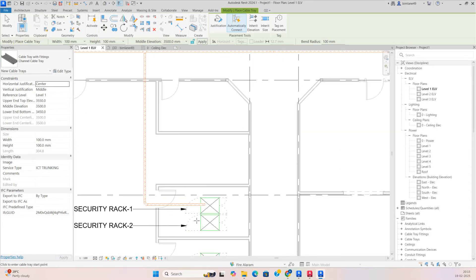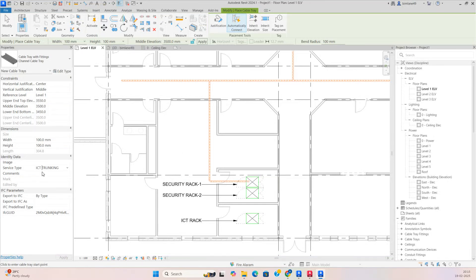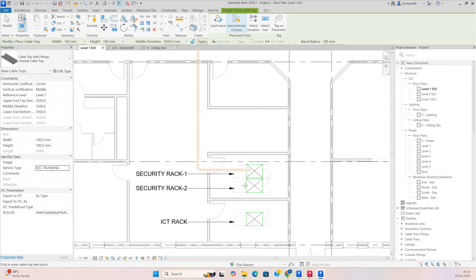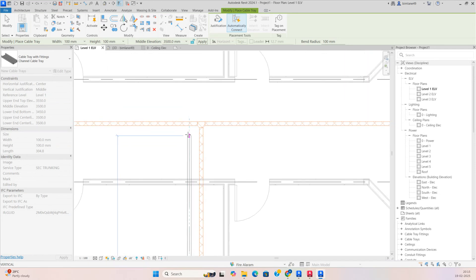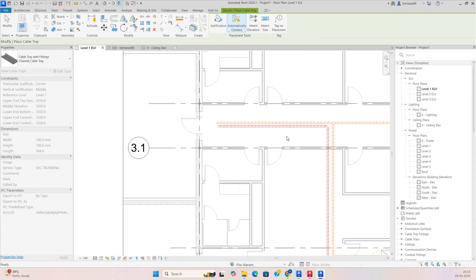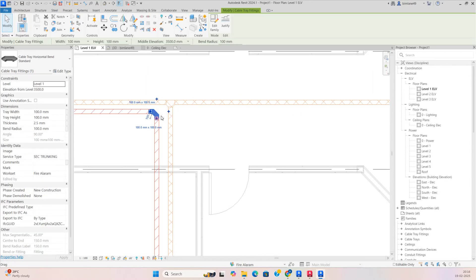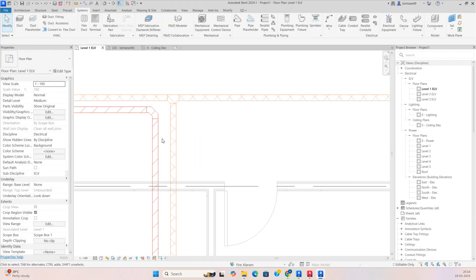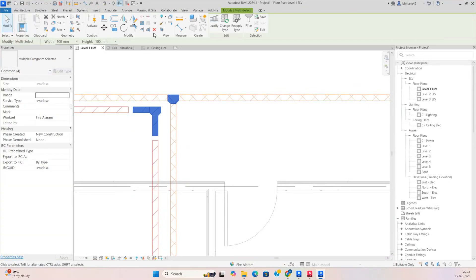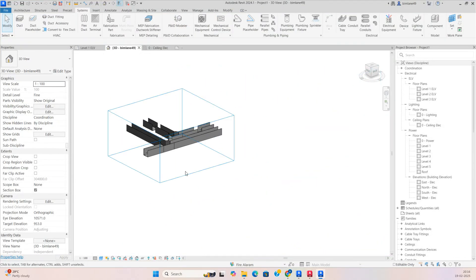For another cable trunking, for the security system, just change the service type to Security Trunking, then draw the trunking with the same elevation. If you try to cross at the same elevation it will clash. To fix this, type SL to split — cut these two portions — so you can add this one separately and change the elevation for that area.